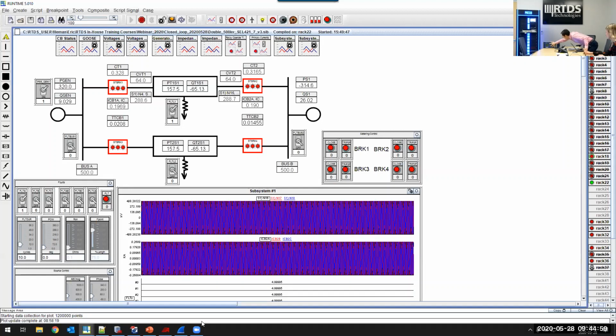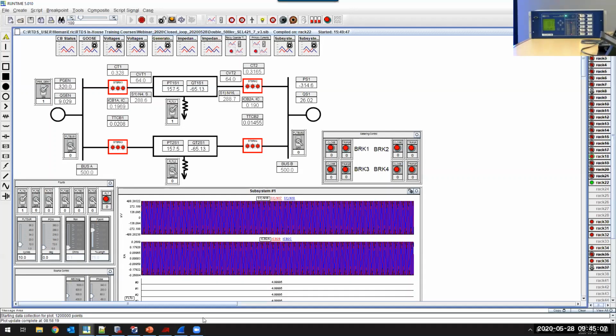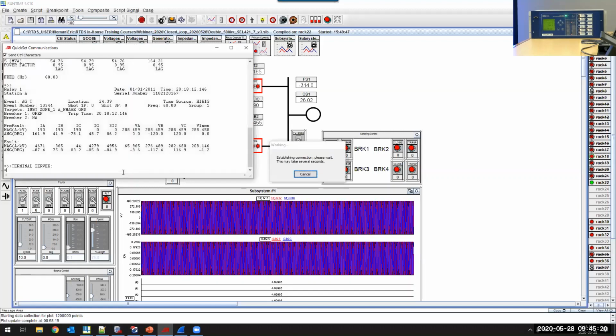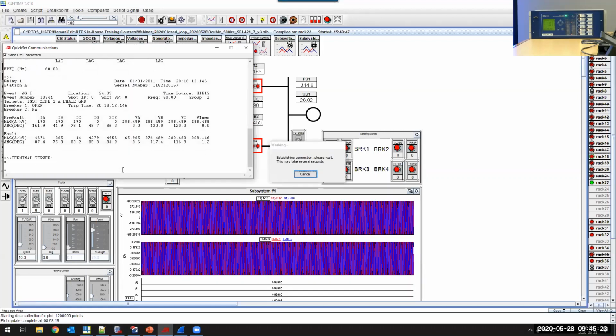One way to verify this is to have a look at the front panel of the relay. Probably you can see the values that are read by the relay. The voltage is 288.5 kilovolts. Current is 189 point something. The other option is to use this embedded HIL terminal.